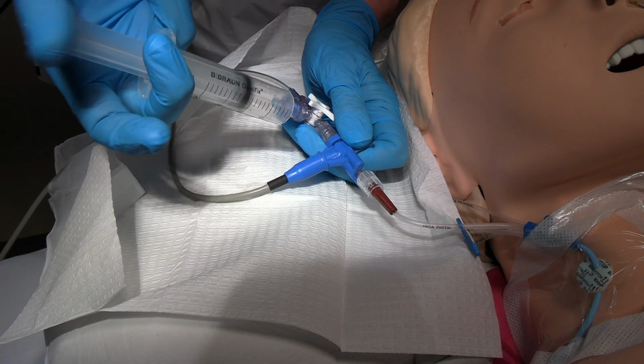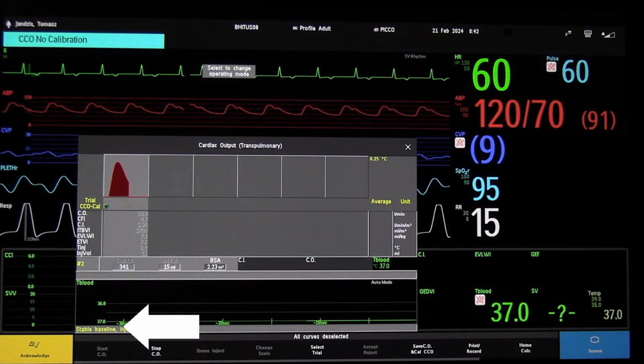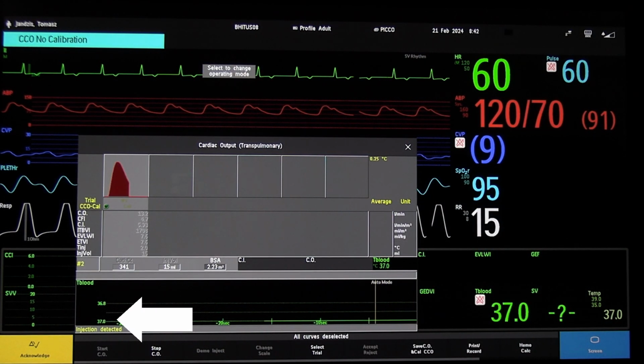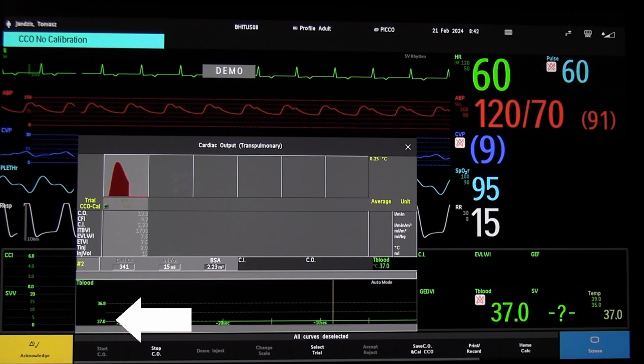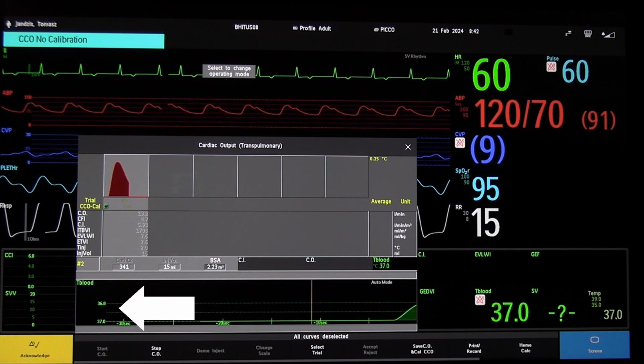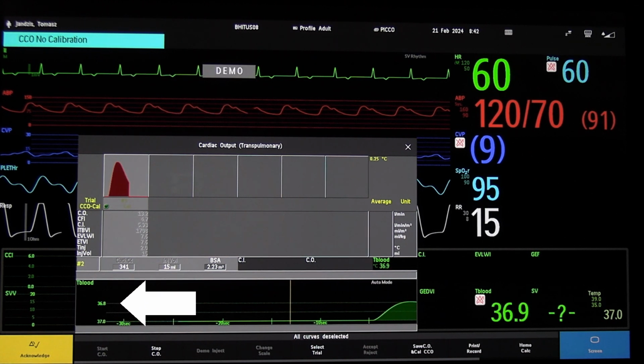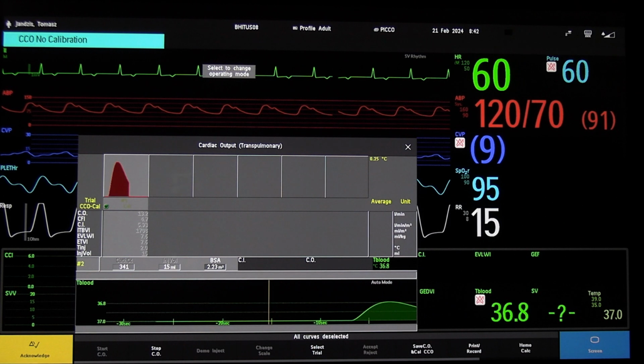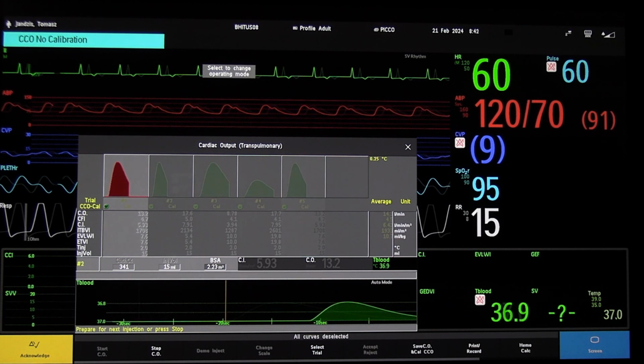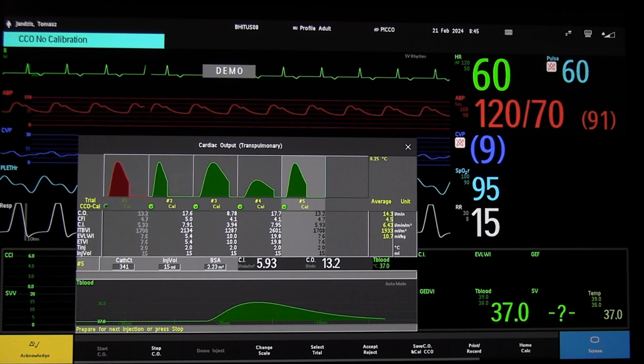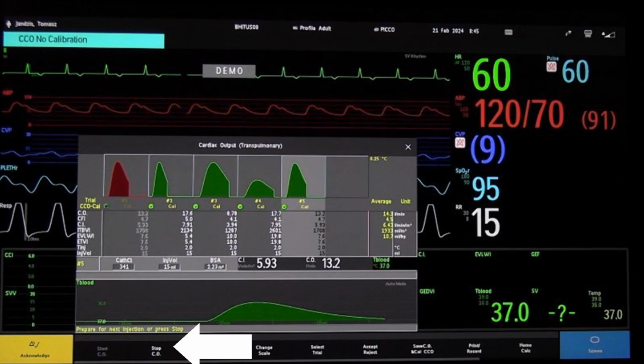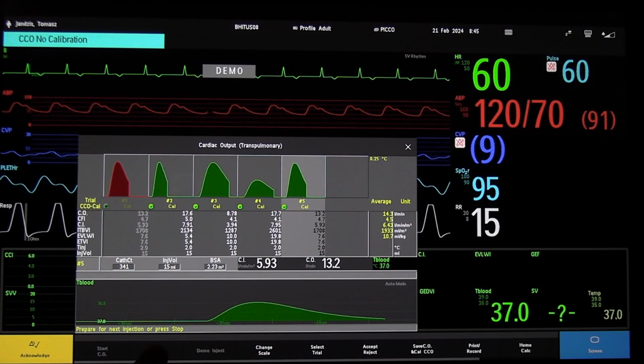Once the injection is detected, the actual procedure begins, and a green curve will build up on the screen. Please note that the bottom line indicates the actual patient's temperature, while the line above marks 0.2 degrees Celsius below. The rising curve must cross this level for the injection quality to be sufficient for PiCCO calibration. Repeat the procedure a minimum of 3 times. If the quality of one injection is not satisfactory, repeat it when prompted by the monitor. To stop the measuring mode, press the Stop PiCCO button on the screen.